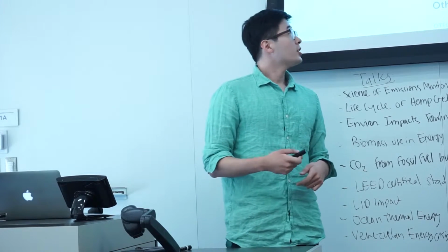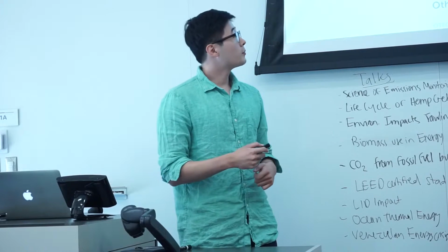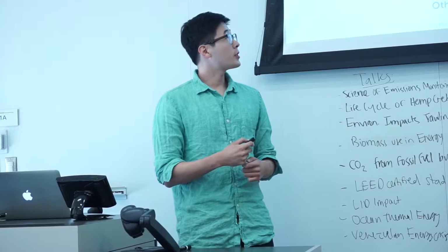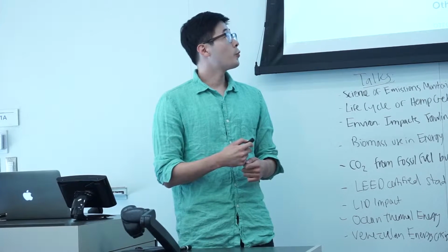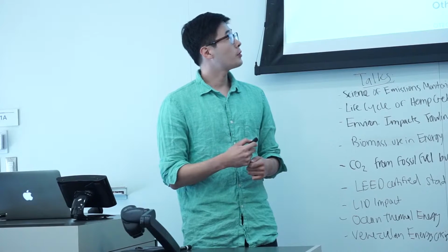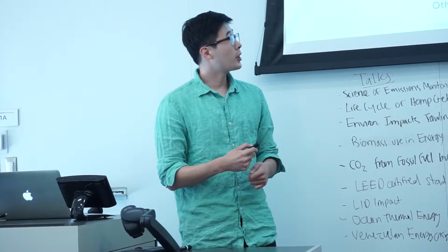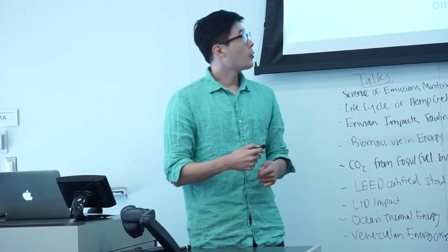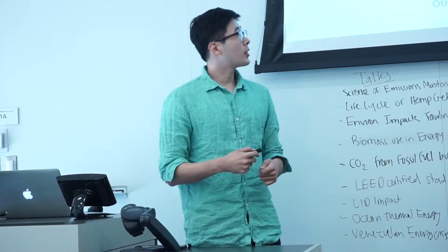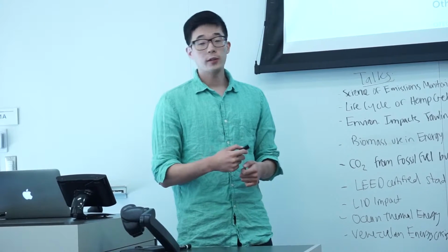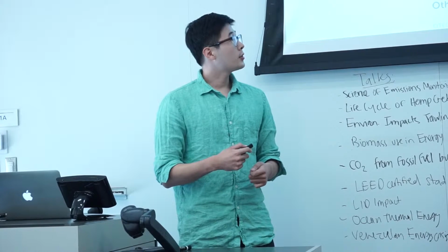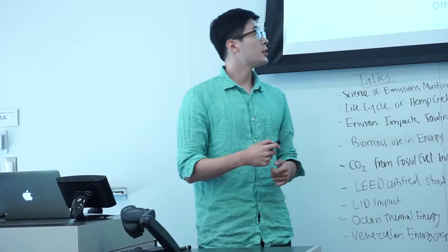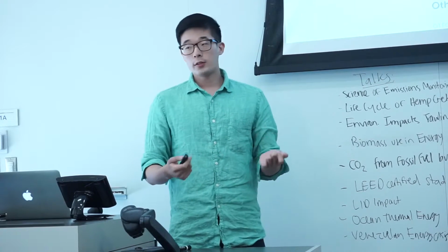The last cycle I want to mention is the hybrid cycle, where the warm sea surface water is again pumped. But this time it's flash evaporated in a vacuum tank and becomes a steam, where the steam boils the low boiling point fluid, ammonia, and that ammonia generates electricity. And the rest of the steam goes into a flash chamber, where it's condensed by the same cold seawater that condenses both the working fluid and the steam, where this working fluid is recycled back to generate electricity and the steam is produced as freshwater discharge.